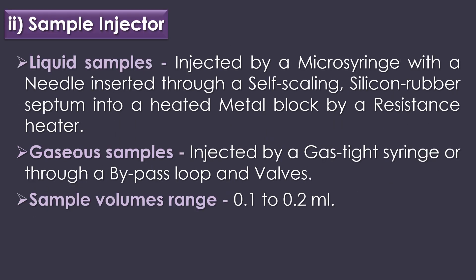The second part of gas chromatography is the sample injector. Liquid samples are injected by a microsyringe with a needle inserted through a self-sealing silicone rubber septum into a heated metal block. Gaseous samples are injected by a gas-tight syringe or through a bypass loop and valves. A typical sample volume used for gas chromatography analysis ranges from 0.1 to 0.2 ml.